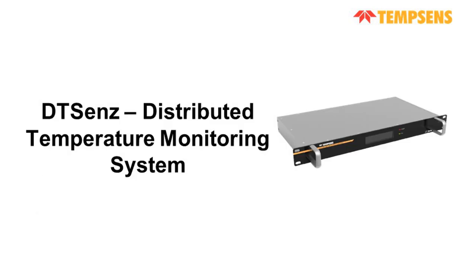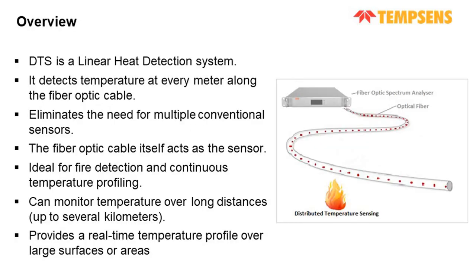Moving on to our third solution, that is Dtsenz, distributed temperature monitoring system. Let me introduce to you distributed temperature sensing, or DTS. It is a linear heat detection system that doesn't rely on multiple traditional sensors. Instead, it uses a single strand of fiber optic cable to continuously measure temperature along its entire length, detecting changes at every meter. So using a single fiber optic cable, you can measure temperature up to kilometers.